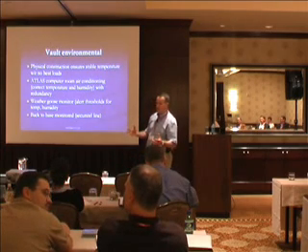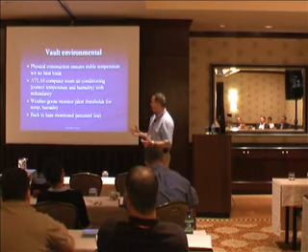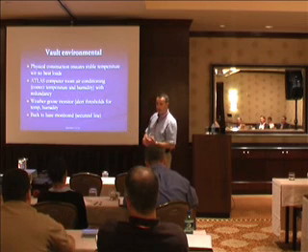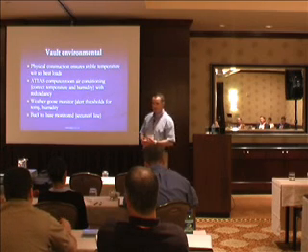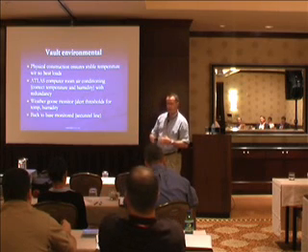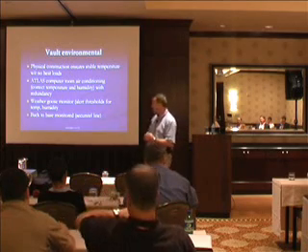The physical construction of the vault gives us extremely good environmentals. So we've got a concrete slab, we've got double brick wall around the whole thing. This place is not going to change temperature that much, but we're going to use the existing air conditioning system we have in our current vault, which is an Atlas computer room air conditioner, and that gives us the correct temperature and humidity. And I stress humidity because, like Houston, Sydney's similar, very hot, very humid at times. Got to keep those tapes happy, the right temperature.